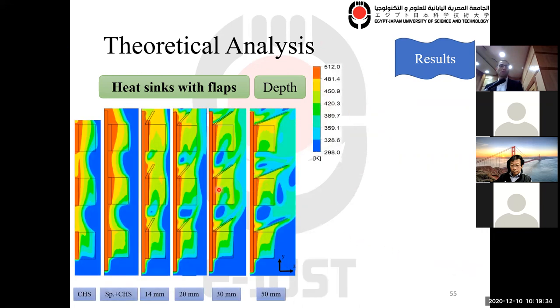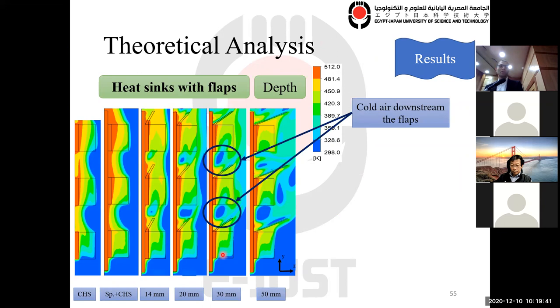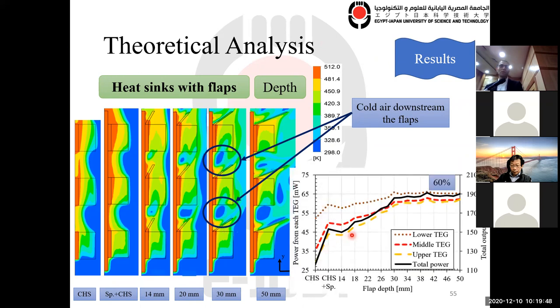To understand the reason behind this, increasing the flap depth leads to the forming of a cold spot downstream of the flap, because the flow is deflected away from the chimney, leading to cold air entrainment in this location, which leads to improvement in performance up to 60% in total output. In the case of increasing the flap depth beyond 30 millimeters, which is the same length as the fins, the cold spot forms in a location that does not affect the performance of the heat sinks.